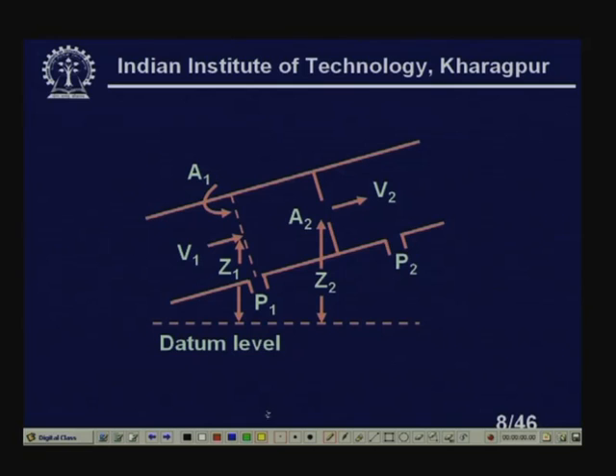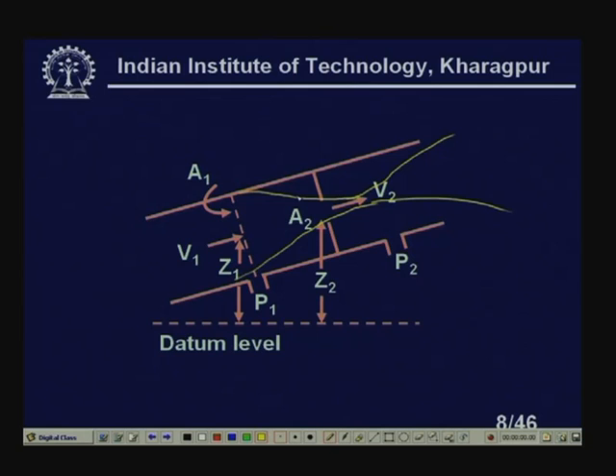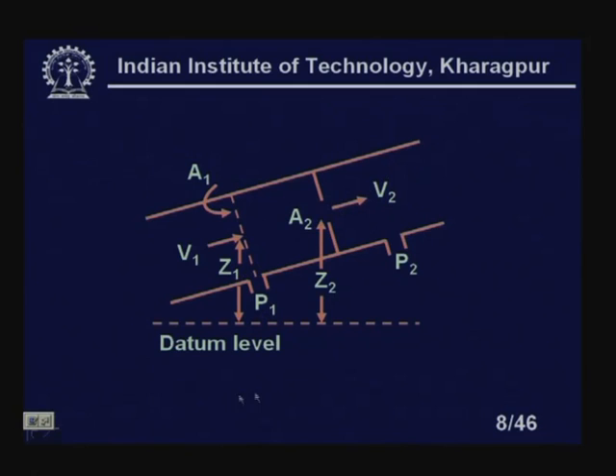The liquid flows and there is a minimum pressure area after the orifice — the vena contracta. The area of cross section upstream is A1, and the area at the restriction is A2. P1 is the upstream pressure tap and P2 is the downstream pressure tap. Z1 and Z2 are the heights of the central point of the pipe cross section at the upstream and orifice measurement points respectively.